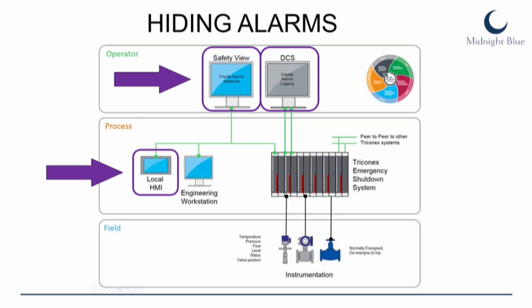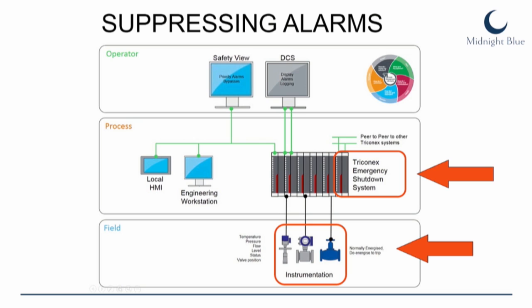So how do we go about this? We can hide the alarms by compromising the safety view or the DCS view or some local HMIs. This is the benefit of hiding them centrally, but still these alarms go out as network traffic, and we don't want any kind of network inspection to see these alarms. So we want to suppress them either at the field level, the level of the field devices, or at the level of the safety controller itself, which is what Triconex is.